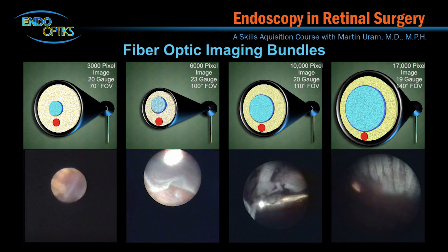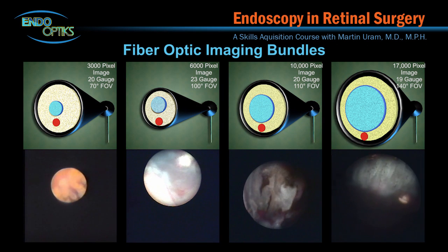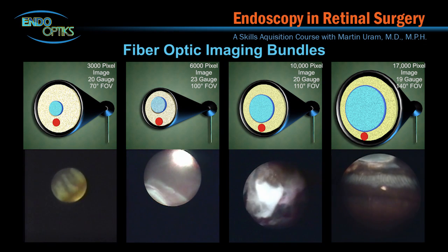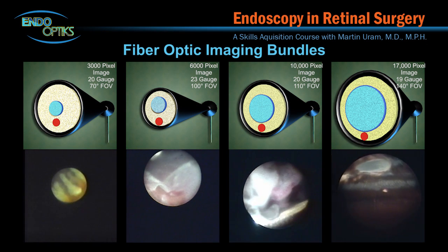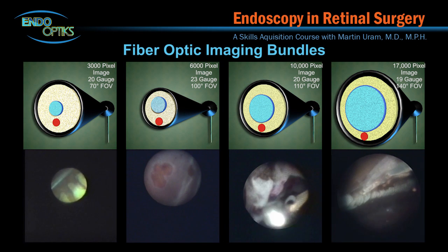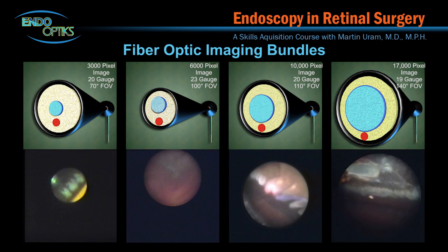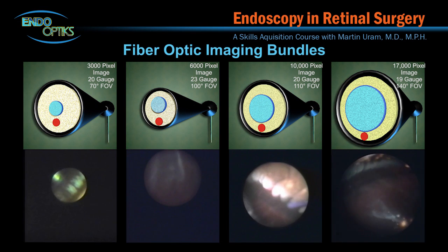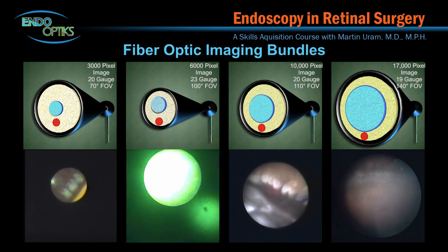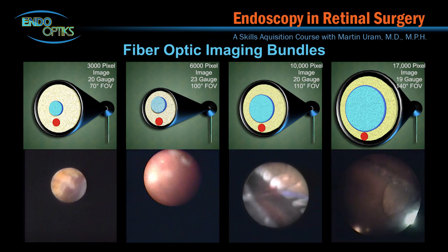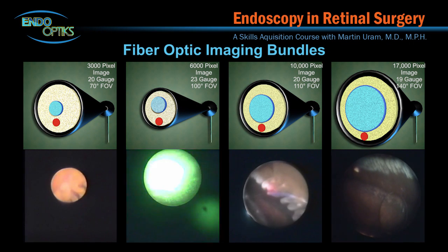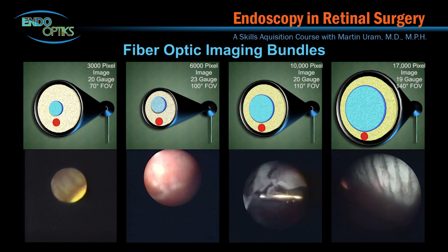Fiber optic image resolution is defined by the number of picture elements or pixels. Simplistically put, the higher the number, the better the resolution. Just know that there are other variables that determine image quality besides this feature. The price for more pixels is a larger diameter of the image guide. In the world of micro endoscopy, every 50 microns is significant, and so the surgeon must sometimes trade off better resolution for a smaller size.